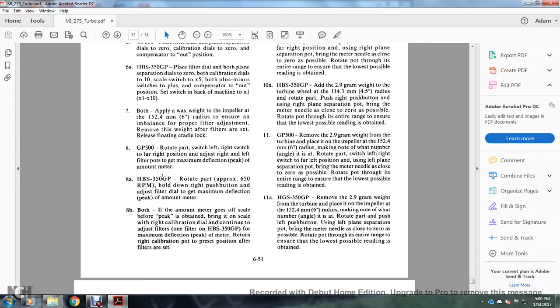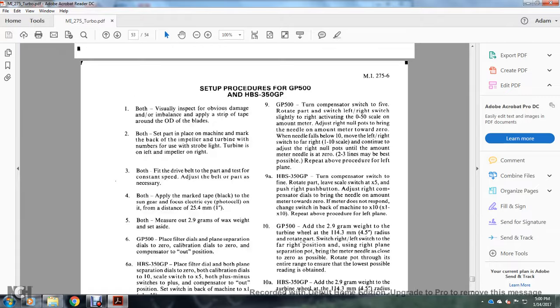The HBS350 GP: rotate at approximately 650 RPM. Hold down the right push button and adjust the filter to get a maximum deflection peak of the amount meter. If the amount goes over the scale before the peak is obtained, bring it into scale with the right calibration dial. Continue adjusting filters on the HBS350 GP for the maximum deflection peak of the meter. Return the right calibration pot to preset position after filters are set.